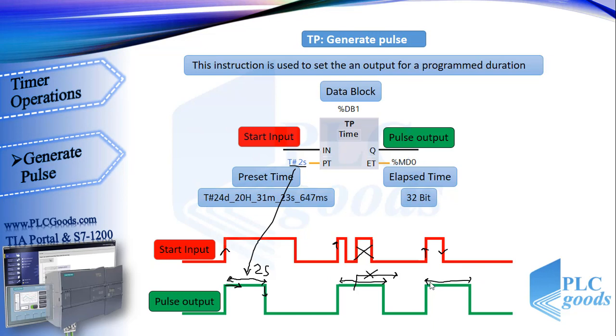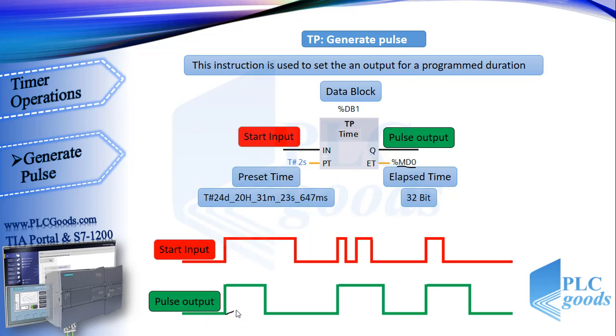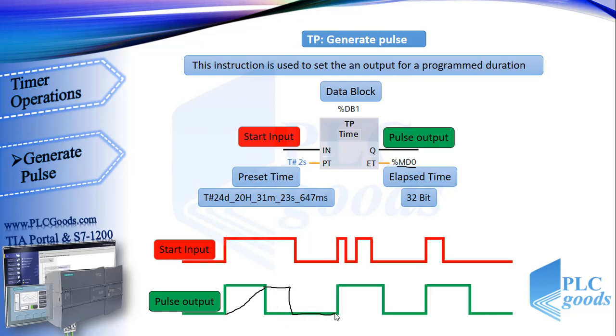Now let me show you a diagram for the ET output which shows elapsed time. When this timer generates a pulse at its first output, the ET output increases linearly. When elapsed time reaches preset time, if the RLO at start input is 1, this output will hold last time until the RLO at start input changes to zero. For next pulse after preset time, the RLO is zero at start input, so ET output backs to zero immediately after two seconds.